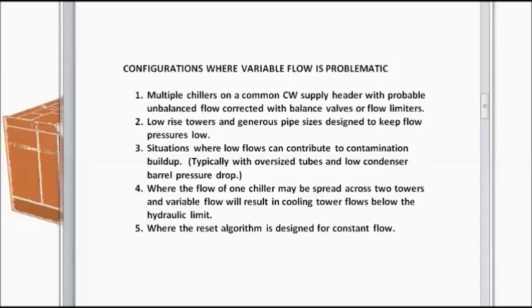And finally, if you are using condenser water reset, and the reset algorithm is designed for constant flow, then that will also limit the potential savings from variable flow.